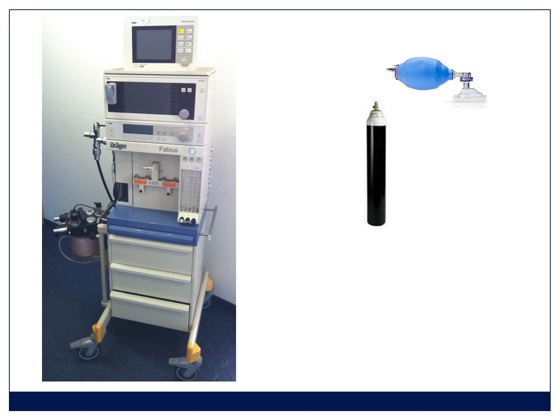The second is a backup oxygen cylinder. Most of your district hospitals are running off a cylinder manifold, which relies on somebody checking these things and replacing them. So it's the sort of thing that can go wrong. And it's very hard to do a general anesthetic without oxygen if you run out. So check your reserve cylinder.